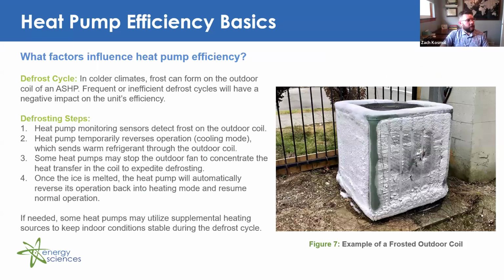So, what other factors influence heat pump efficiency? A defrost cycle is one big one as well. In colder climates, frost can form on the outdoor coil of an air source heat pump, as shown in figure 7 here. So frequent or inefficient defrost cycles will have a very negative impact on your unit's efficiency.